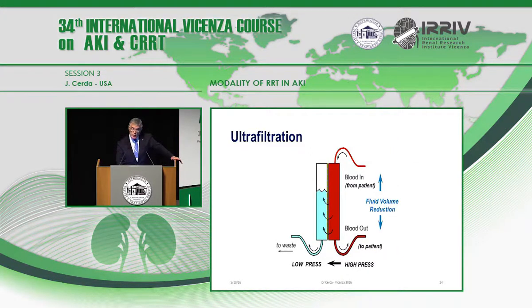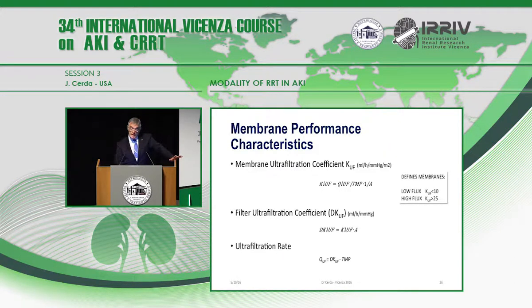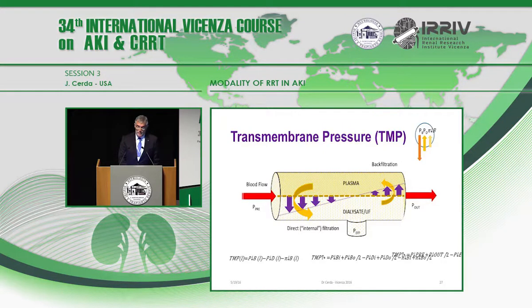In ultrafiltration, the main issue is the removal of fluid across the membrane. That is dependent upon the membrane ultrafiltration coefficient, and the filter ultrafiltration coefficient that is a consequence of that, as well as the area of the membrane.